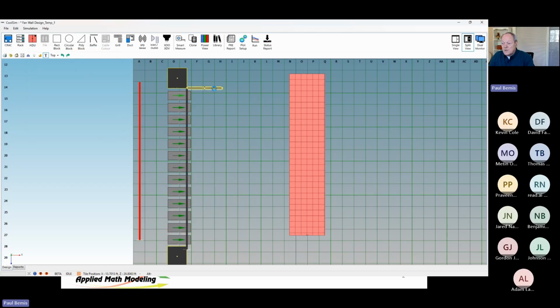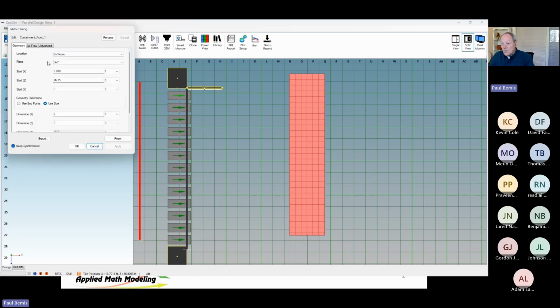3 is too tight. So you want the hot aisle, that's what I'm building here, the hot aisle to be wide enough to meet your needs, okay? I've got a 6-foot hot aisle. So that's really what I want, is something wide enough to be able to handle. And I'll show you, if this number gets too low, you run into pressure problems where the center, the hot aisle, becomes pressurized. Again, due to the fact that we're moving from high velocity air to no velocity air. So if this is not wide enough, you'll get a pressure gradient in the center of the hot aisle caused by 2 flow streams intersecting with one another. So I'm 6 foot here, that's fine.